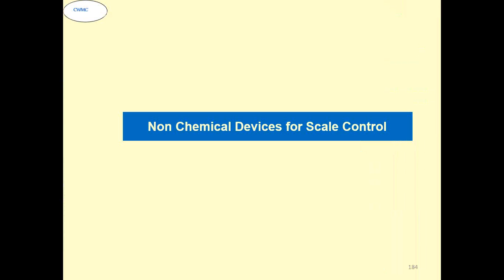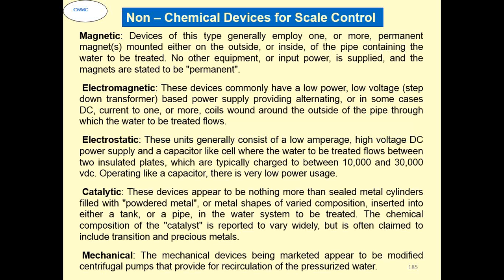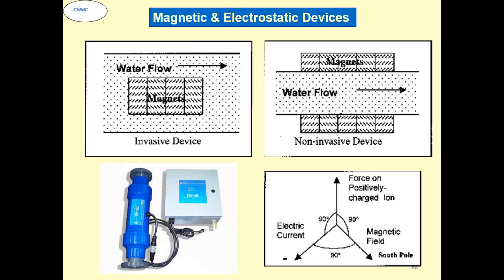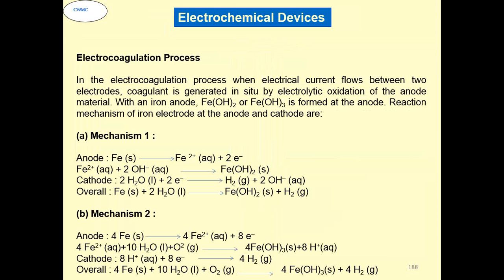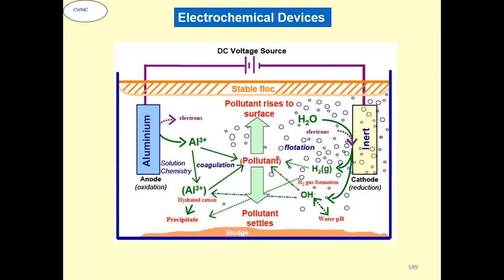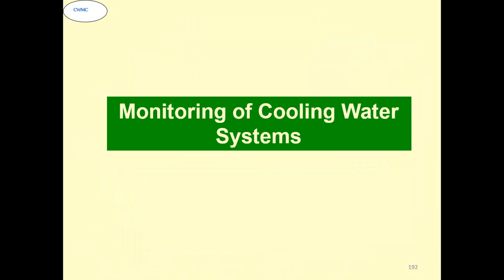See, I have put something here because nowadays many people come out with non-chemical devices for scale control. There can be magnetic, electromagnetic, electrostatic, catalytic or mechanical devices, different kinds of things which are available in the market. There is an electrocoagulation process in which, through electrochemical principles, the ions are separated out and you get the proper treatment. These are typical devices. But my comment is, most of the time these non-chemical devices have been found to be good for smaller systems. Very rarely have they been found to be good for big systems.